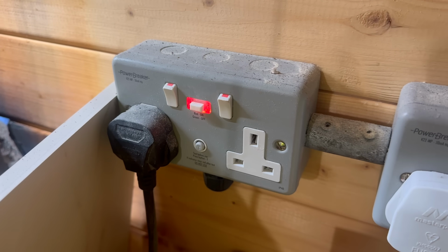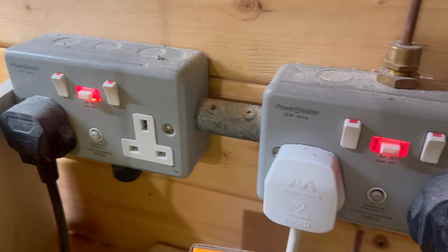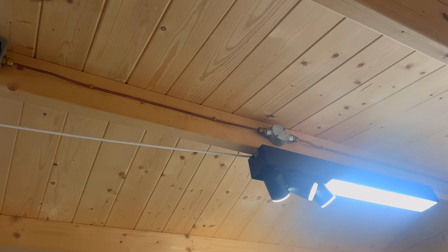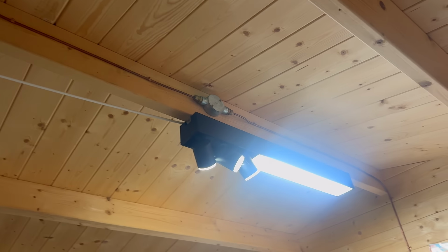Inside we do have metal accessories, sockets, containment and a short run of MICC, but all of that metalwork is part of the electrical installation. It is not an extraneous conductive part with an independent connection to earth. So from an earthing point of view, this is a non-conductive location.